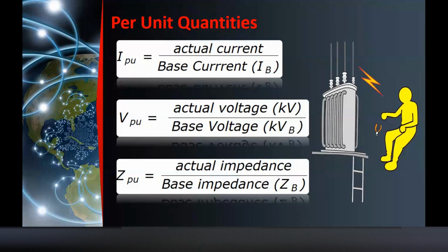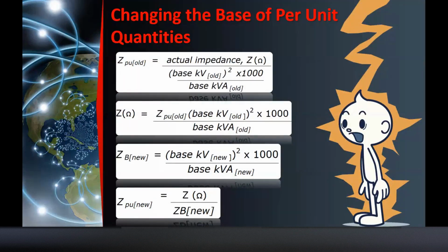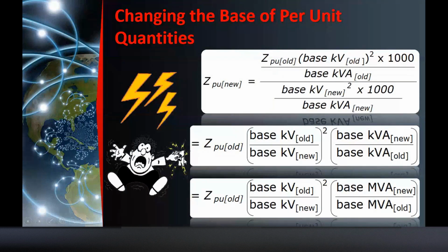Okay? Your V per unit or your voltage per unit is simply actual voltage divided by your base voltage. And your impedance per unit, actual impedance divided by your base impedance. This last formula, the impedance, is what is used in sizing resistors, no? This one, when you see that formula, you can use it. This one, very common. The old impedance, you can convert it to the new impedance by using this formula. Like I said, I can't give the derivation, but the copy of my presentation has the derivation. Class, that is your homework.